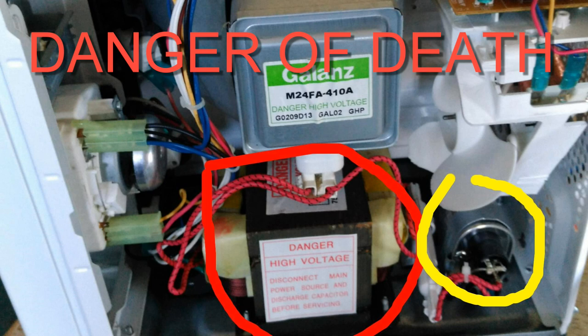But basically, you have to make sure that that capacitor is fully discharged. Most of them have a bleed resistor wired across them so that they will self-discharge in a matter of minutes. But that's not a safe assumption to make. They've been known to fail. So you have to discharge that capacitor before you go anywhere near salvaging the component you need.